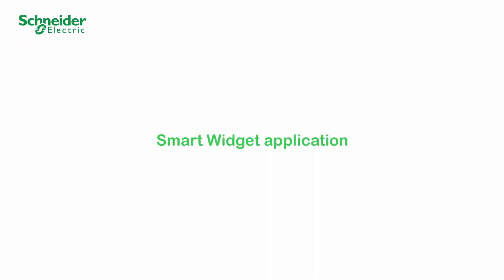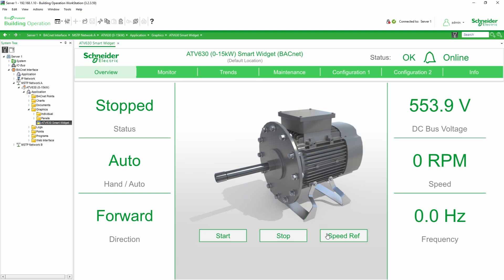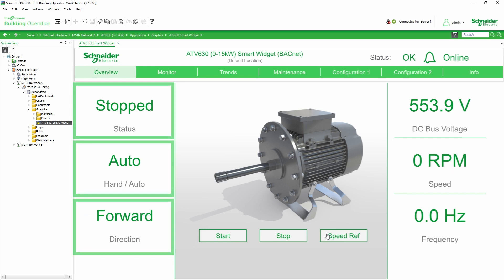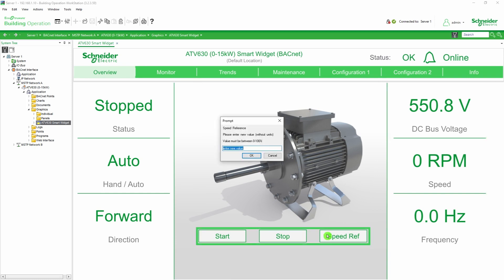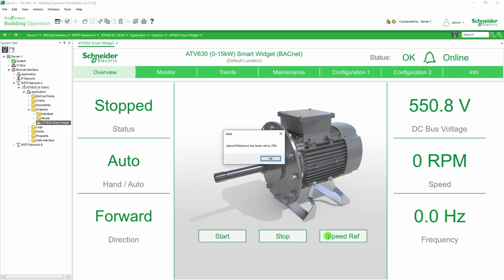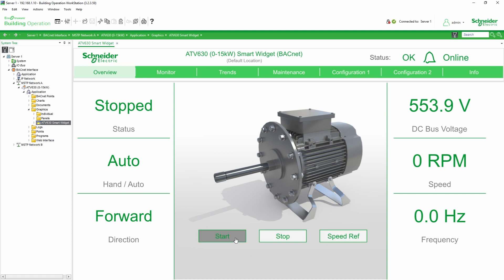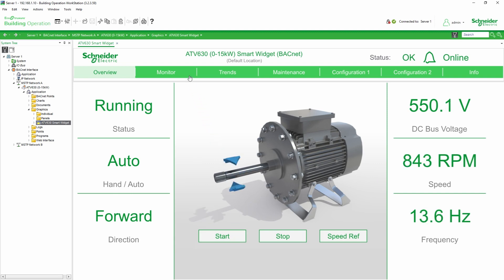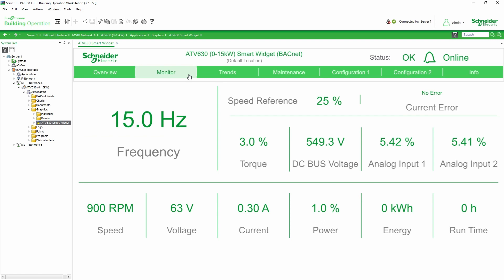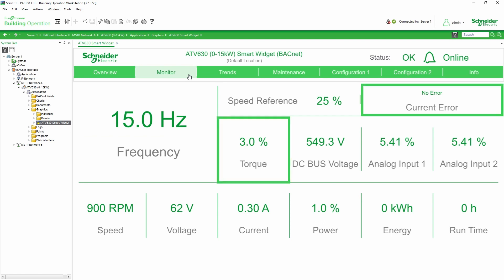SmartWidget application. The overview is a semi-configurable dashboard where you can see the motor status, control mode, and direction of the rotor. The right panel is customizable via the configuration tab. You can also set a speed reference and start or stop your motor. We start the motor. In the monitor tab, you can monitor the main values of the drive application in real time, such as current error status, torque, speed, and so on.